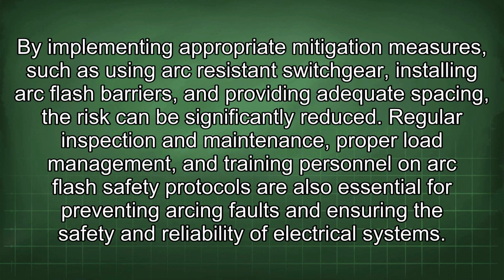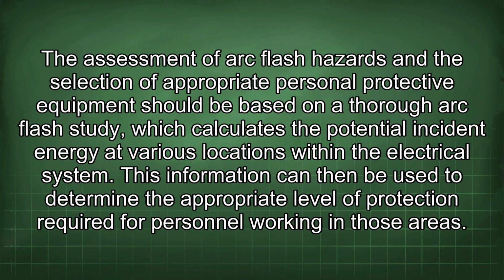By implementing appropriate mitigation measures such as using arc-resistant switchgear, installing arc flash barriers, and providing adequate spacing, the risk can be significantly reduced. Regular inspection and maintenance, proper load management, and training personnel on arc flash safety protocols are also essential for preventing arcing faults and ensuring the safety and reliability of electrical systems. The assessment of arc flash hazards and the selection of appropriate personal protective equipment should be based on a thorough arc flash study which calculates the potential incident energy at various locations within the electrical system. This information can then be used to determine the appropriate level of protection required for personnel working in those areas.